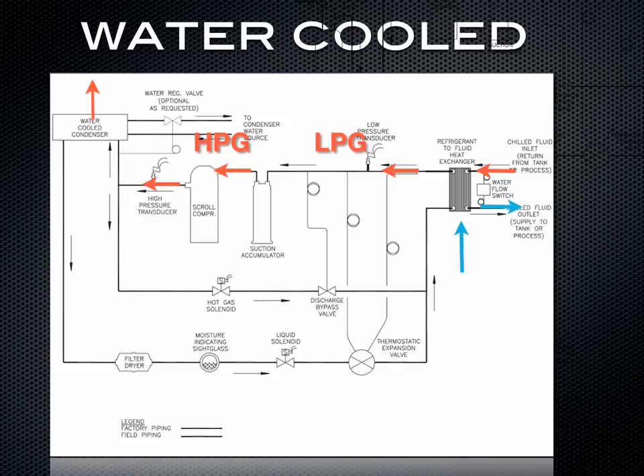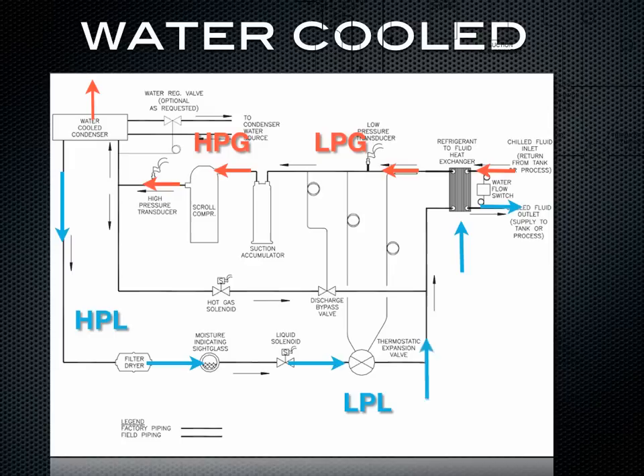Once it leaves that water-cooled condenser and the heat's been rejected, it's going to have a state change to a high-pressure liquid. It's going to leave the filter dryer and go through the sight glass, and it's going to go to the thermal expansion valve right here. What happens in the thermal expansion valve is it comes from a high-pressure liquid and basically has a pressure drop to a low-pressure liquid. Then it will go back to the chiller evaporator and that whole process will repeat.